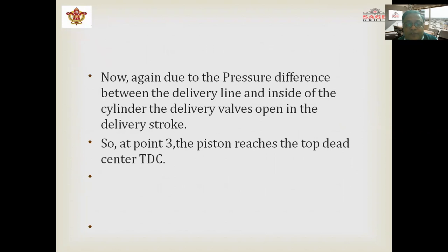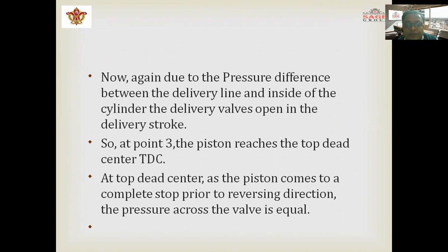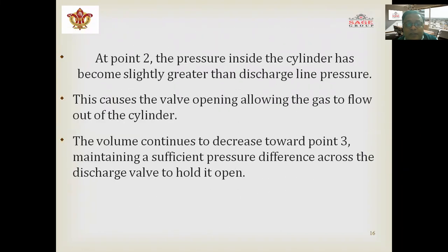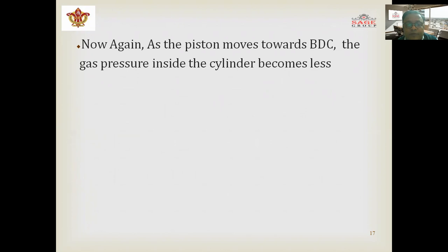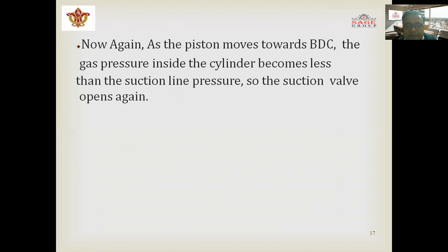Due to the pressure difference between the delivery line and inside the cylinder, the delivery valve opens. At point three, the piston reaches top dead center (TDC) and comes to a complete stop prior to reversing direction; the pressure across the valve is equal, so the discharge valve closes. At point two, the pressure inside the cylinder becomes slightly greater than the discharge line pressure, causing the valve to open and gas to flow out. The volume continues to decrease towards point three, maintaining sufficient pressure difference to hold the discharge valve open. As the piston moves back towards BDC, the gas pressure inside becomes less than suction line pressure, so the suction valve opens again, and the cycle repeats.